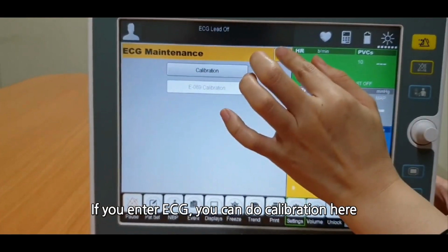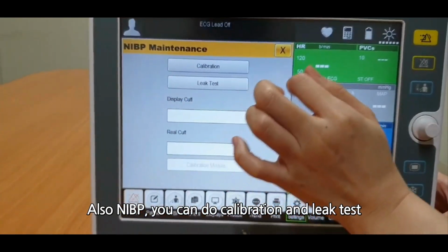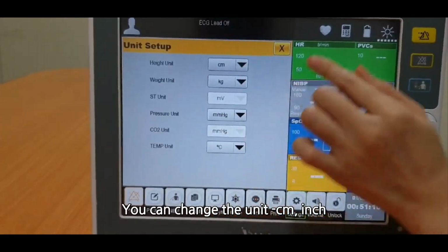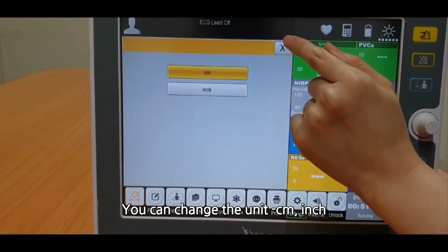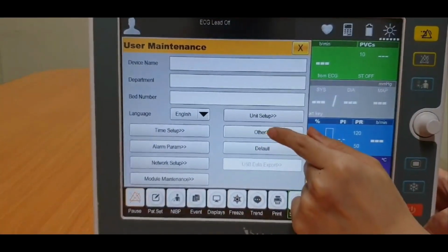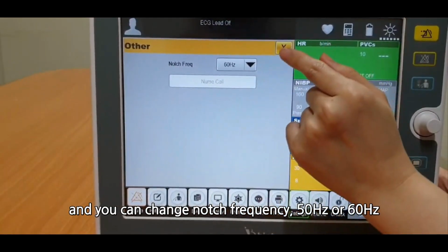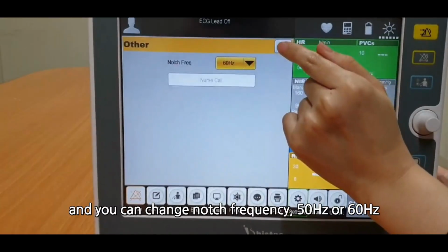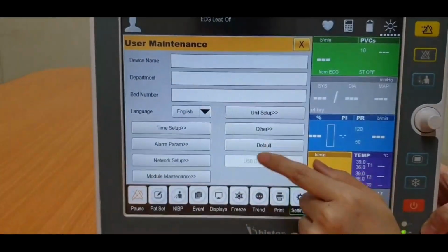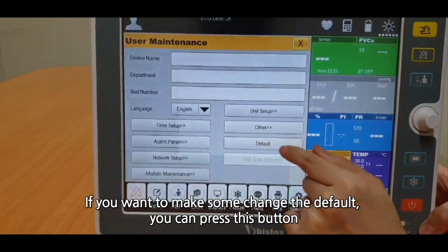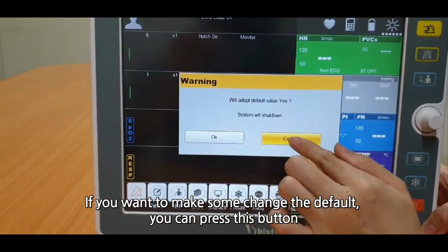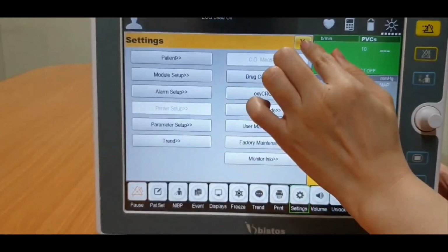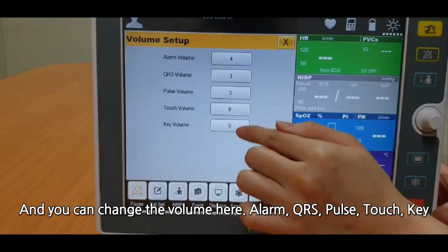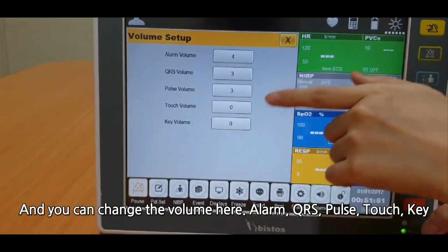And module maintenance. If you enter ECG, you can do calibration here. Also NIBP, you can do calibration and leak test. You can change the unit, centimeter or inch. And you can change the notch frequency, 50 or 60 Hertz. If you want to make changes to the default, you can press this button. And you can change the volume here: alarm, QRS pulse, touch, and key.